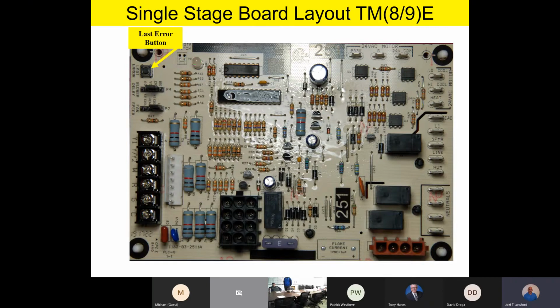As we move around the board, you'll notice there's a flashing LED. This flashing LED is actually a fault or status LED. That status LED will flash one of 3 colors: red, green, or yellow, based on the flash code. It should be noted that the LED is going to give you various flash codes or fault codes depending on the fault.